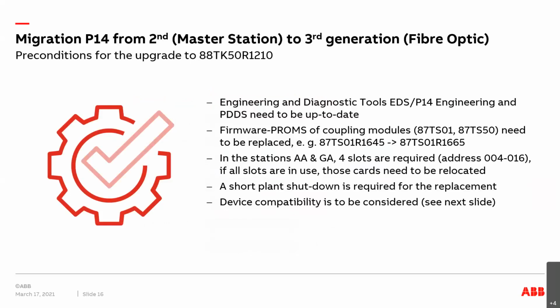First, the engineering and diagnostic tools, as well as the engineering and PDDS, need to be up to date. The firmware of the coupling modules TS01 and TS50 needs to be replaced, meaning they also need to be upgraded. You also have to check that the stations have the first 4 slots free—this is the difference between TK05 and TK50: the TK50 requires 2 slots instead of the 1 slot that the TK05 required.